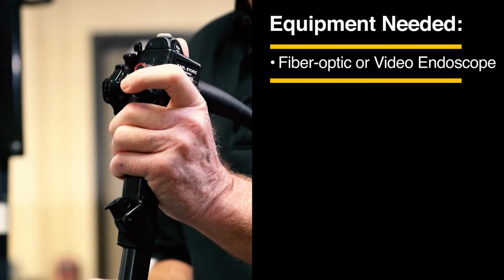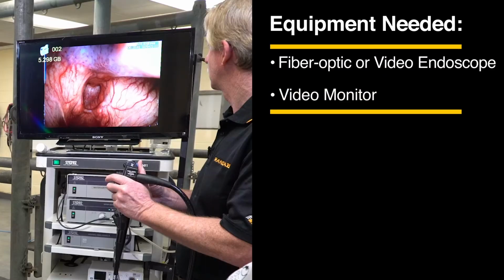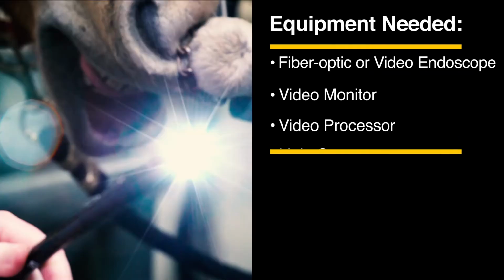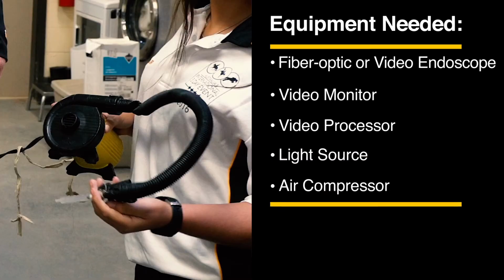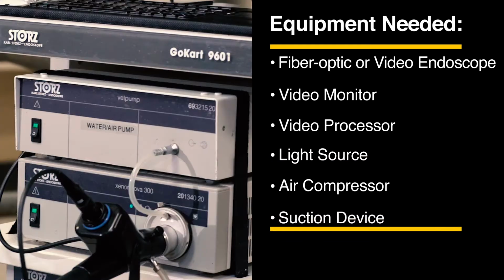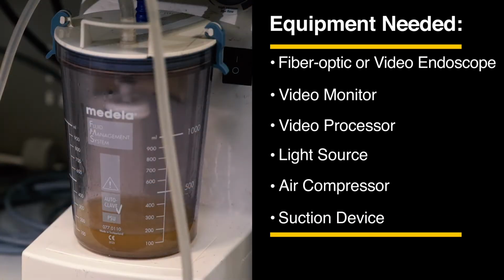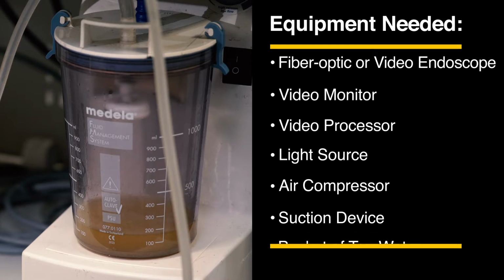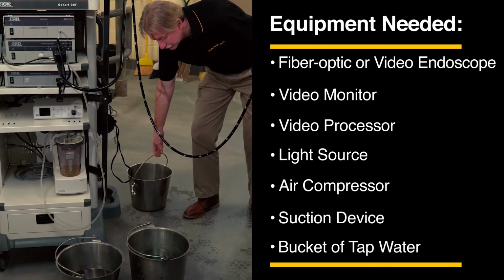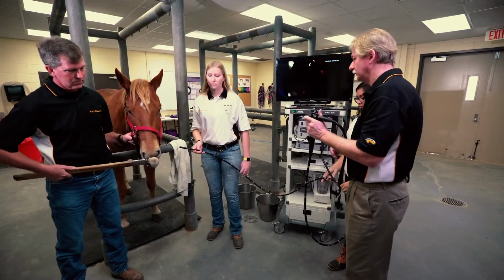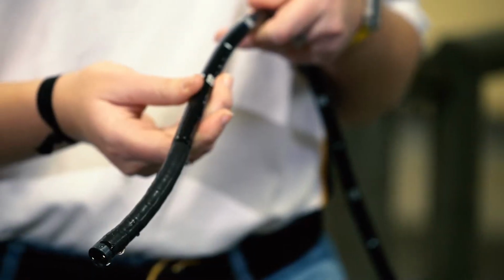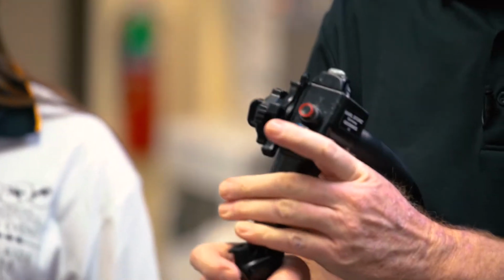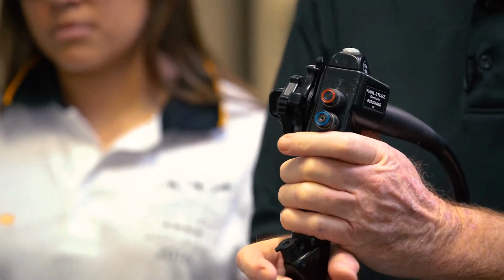The equipment needed for examination of the stomach in standing horses includes a fiber optic or video endoscope, a video monitor, video processor, light source, a small air compressor for insufflation of the stomach, a suction device for aspiration of residual gastric fluid contents and to decompress the stomach at the end of the procedure, and a bucket of tap water for gastric lavage. The endoscope is 3 meters long and 9 to 13 millimeters in diameter and is equipped with a blue air water feed valve and a red suction valve.